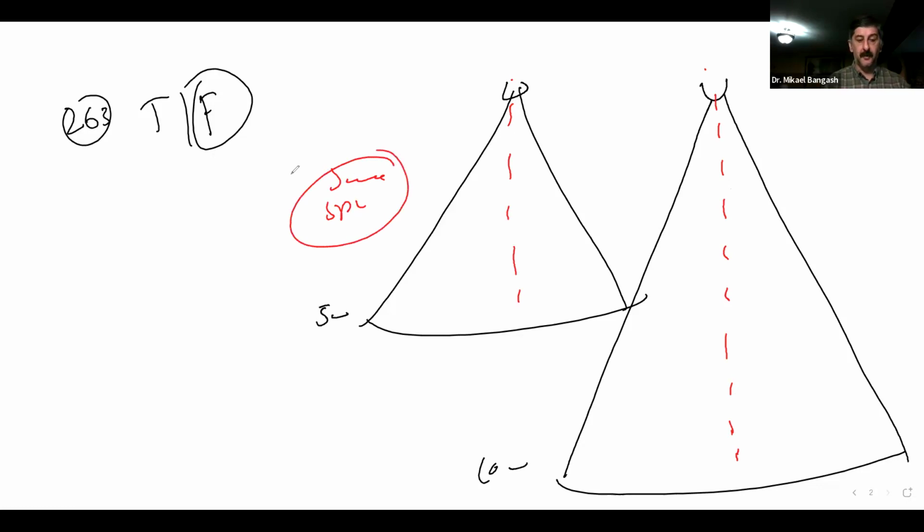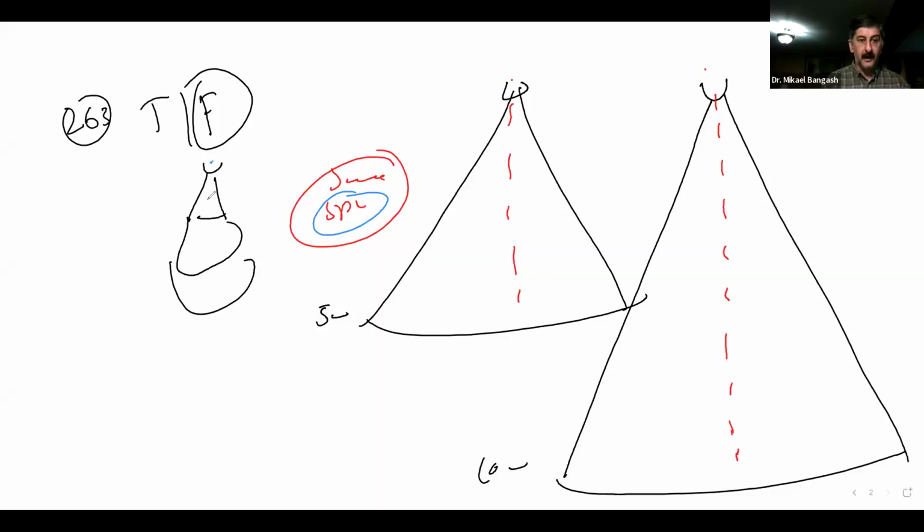So since your spatial pulse length remains the same, adjusting the depth, whether from 5 to 10 centimeters, from 5 to 6, or 5 to 7.5, whatsoever, or the other way around, from 5 to 2.5 or 3 centimeters, is not going to have an effect on the spatial pulse length produced by your system.